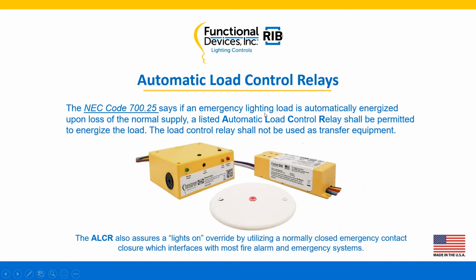The way it kind of is here, if you look at the left-hand side, you'll notice this is an ESRN. You've got a green LED here, that's for normal power. You've got a red LED over on the right-hand side of it. That's for emergency power, and you've got your yellow status, to tell you what the load's actually doing. The other feature of this is a localized test button. And primarily what that's for is when they install this product in the plenum area, there are no bulbs in those fixtures. So they have to make sure they have it wired correctly. So we give them that ability to do that.